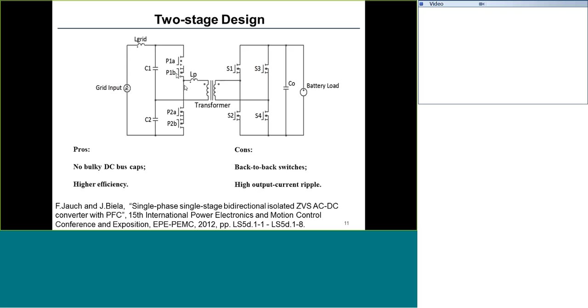Inspired by another paper from ETH, we decided to go for this topology. It totally skips the back-to-back switches and utilizes a silicon-based H-bridge operated at grid frequency. Imagine the grid is 60 hertz - we convert that into 120 hertz DC with the voltage not stabilized, so this voltage profile follows exactly the grid voltage. Therefore we don't need the bulky DC bus capacitor anymore.